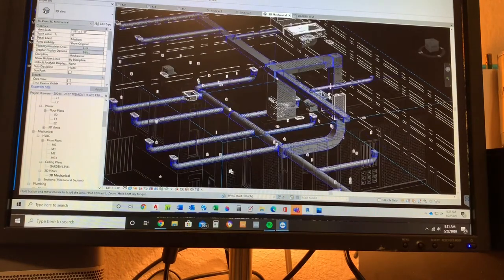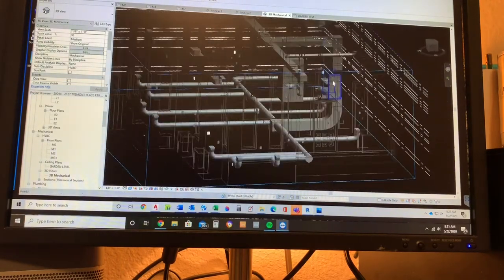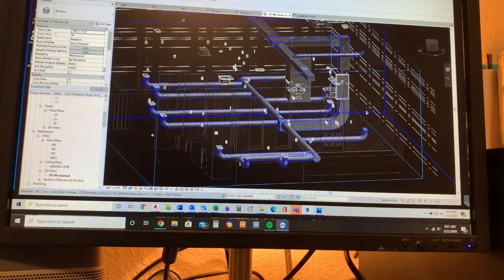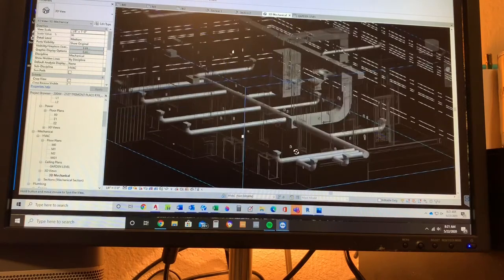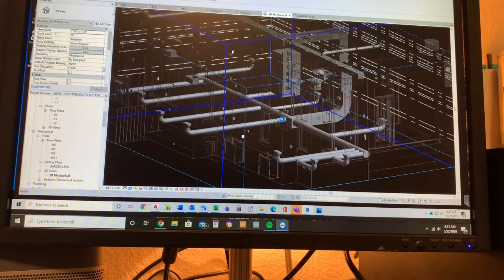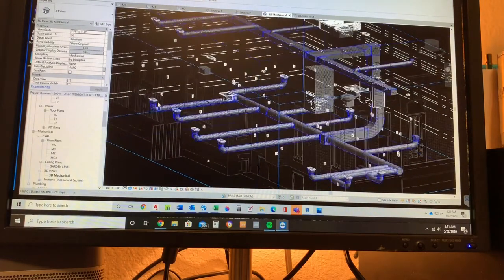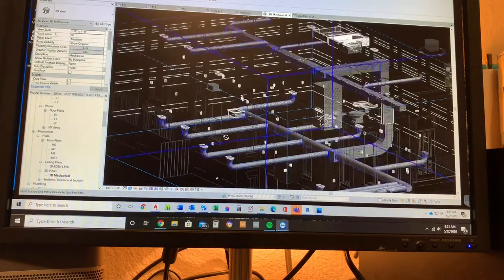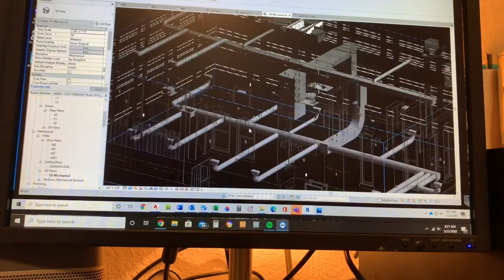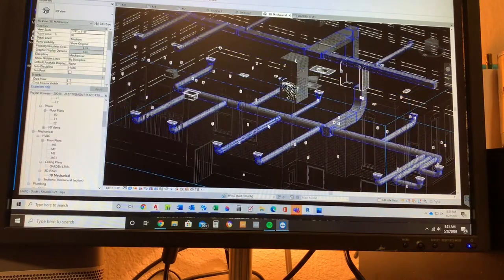We're going to tap off the top with 8-inch rounds, distribute between the joists, and then punch up through the floor for the underfloor distribution. The main level I've sized for a three-ton cooling and heating system. We're going to supply it through spiral exposed duct, which will be visible from the basement tenant — he wanted the industrial finish, so that's what they're going to get. We're going to run the 8-inch taps between the joists and pop up through the floor. This is going to be a fire-rated partition, so we're going to need a damper at each one of these grills coming up through the floor.